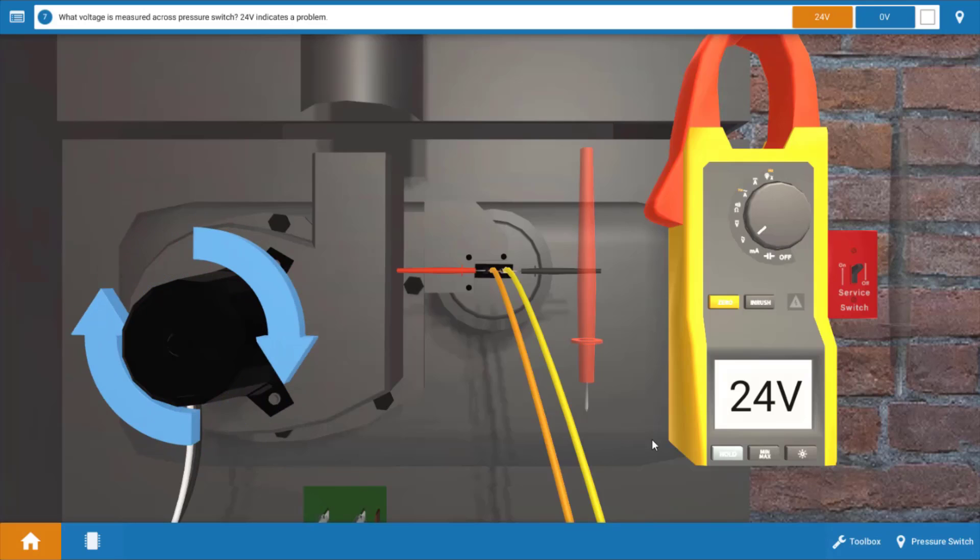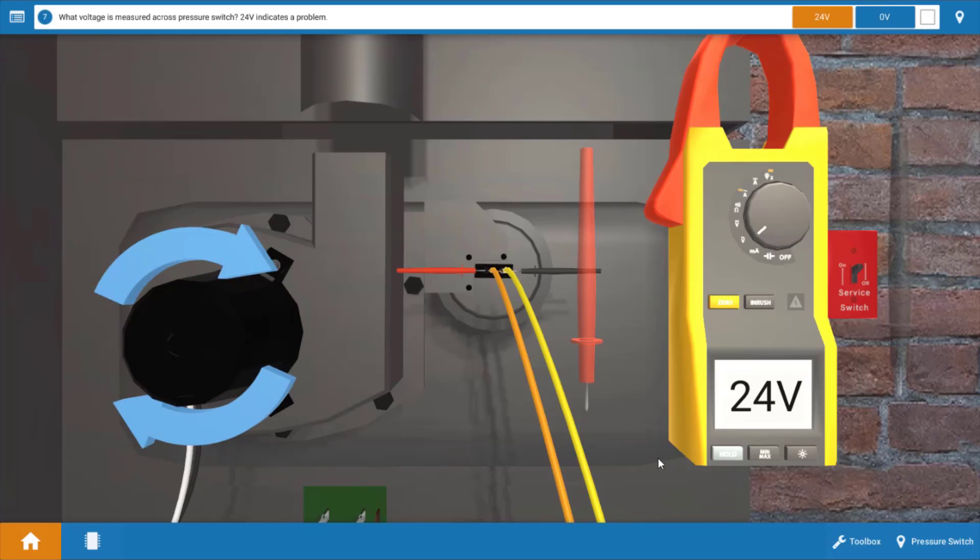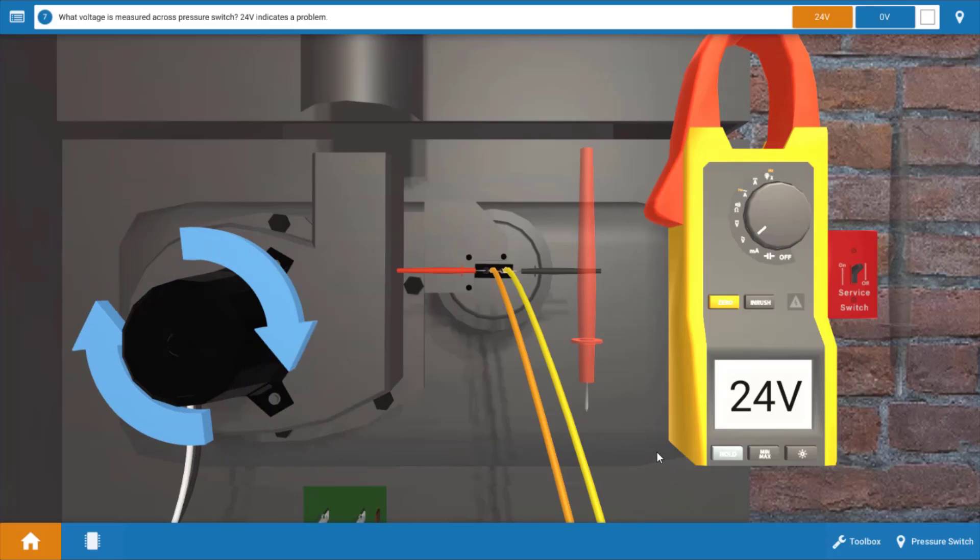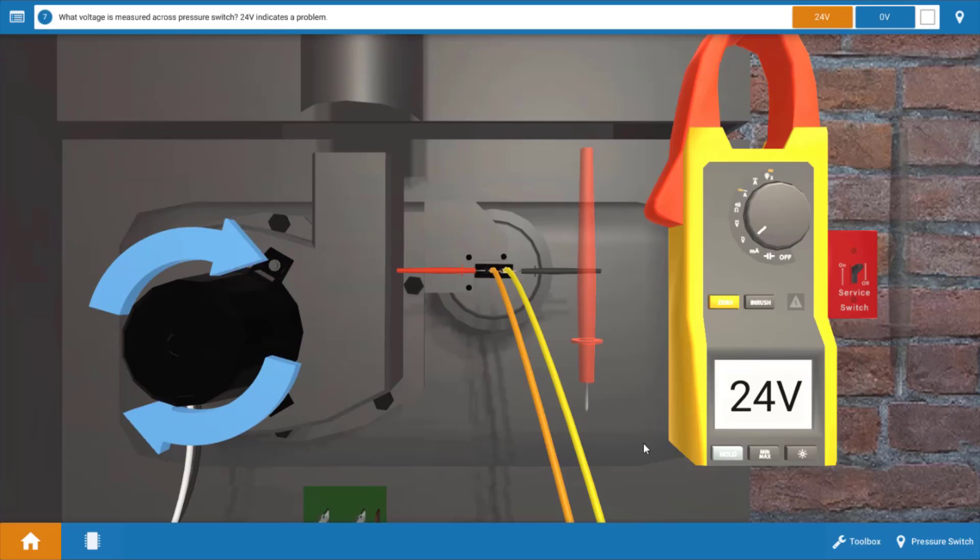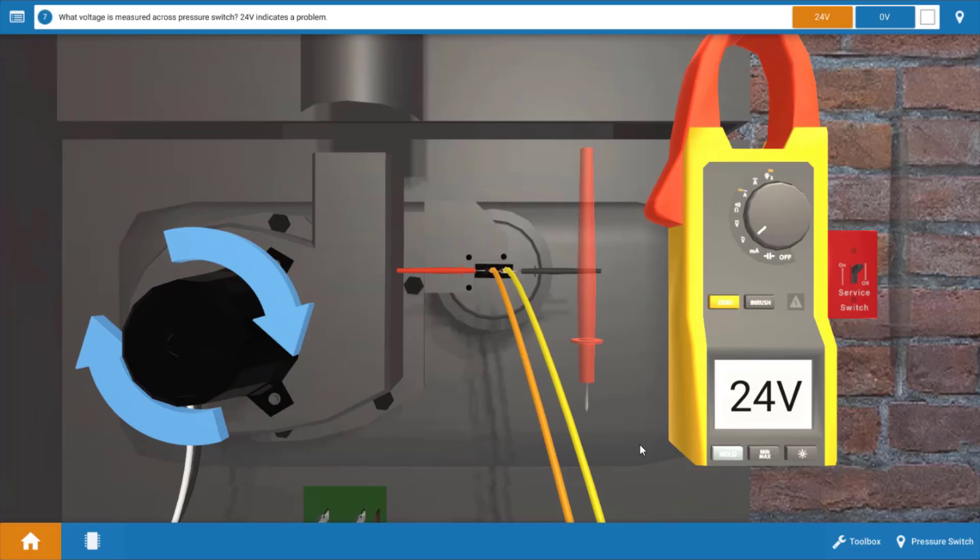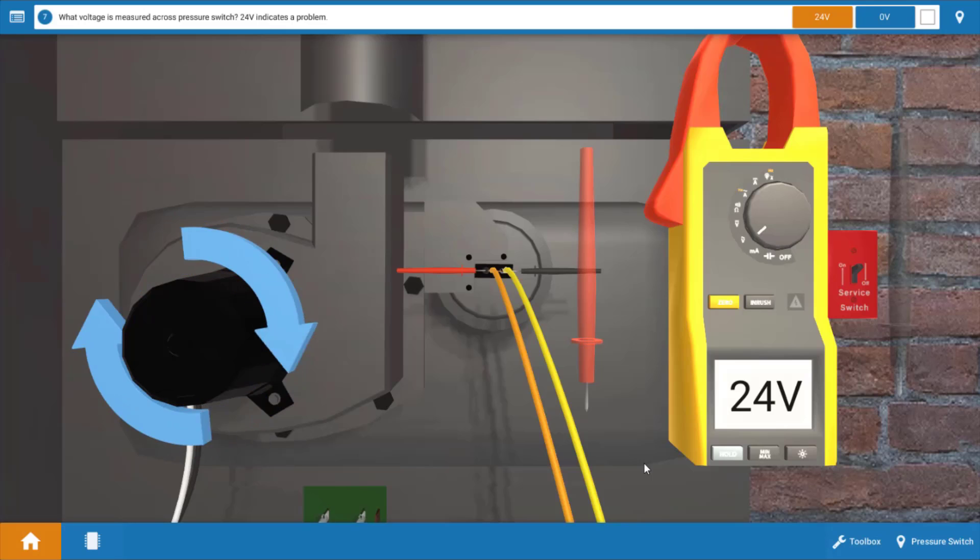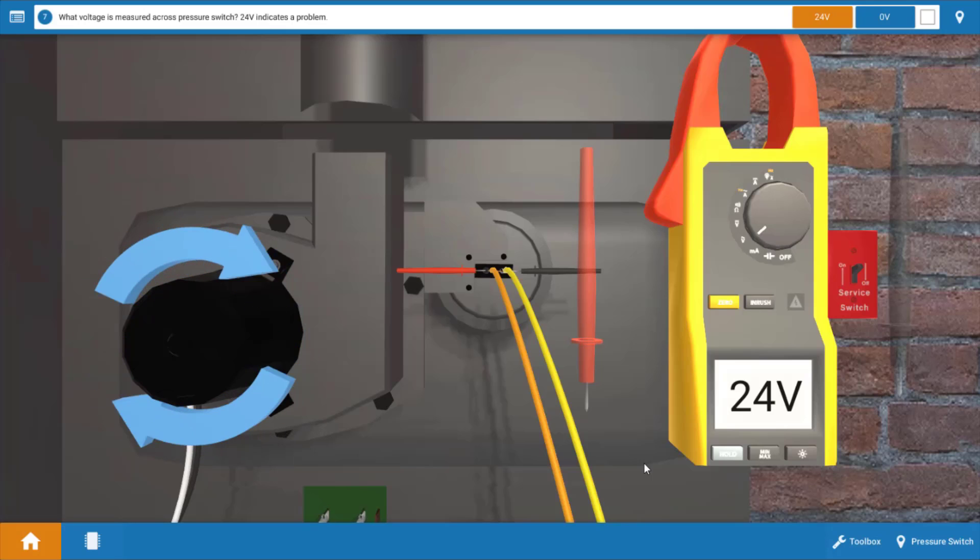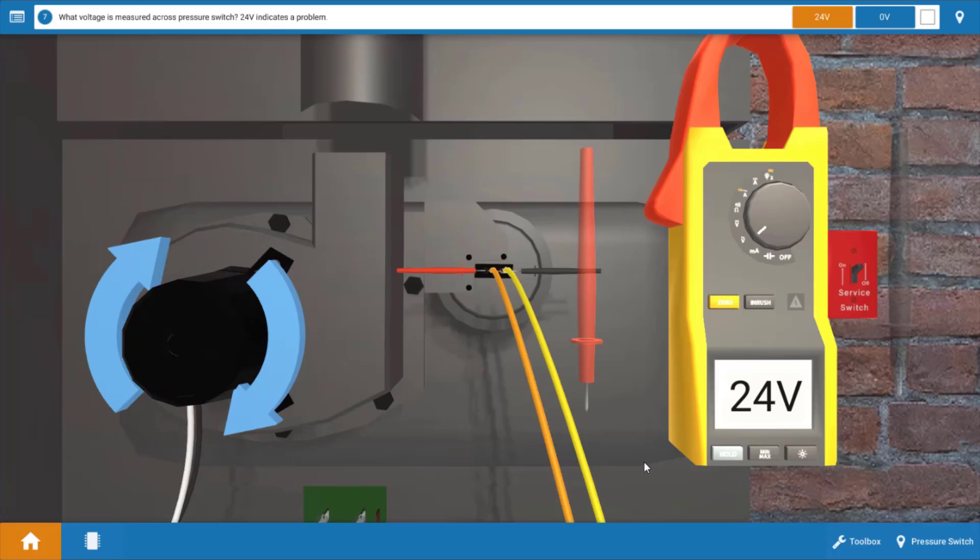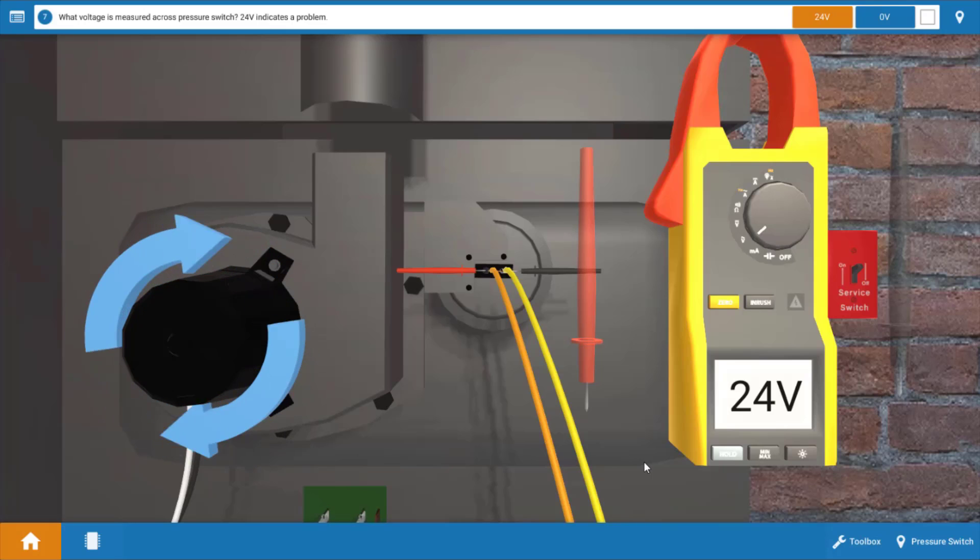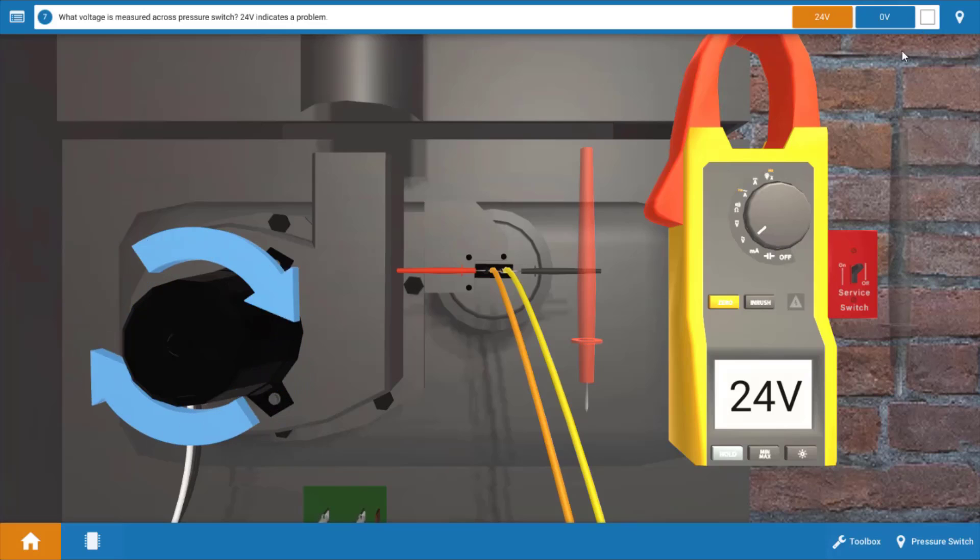Now does this mean the pressure switch is faulty? Usually not. Occasionally you could have a bad pressure switch but most cases there's an obstruction in the vent that's going to cause the pressure switch to open its contacts and not allow ignition of the furnace.